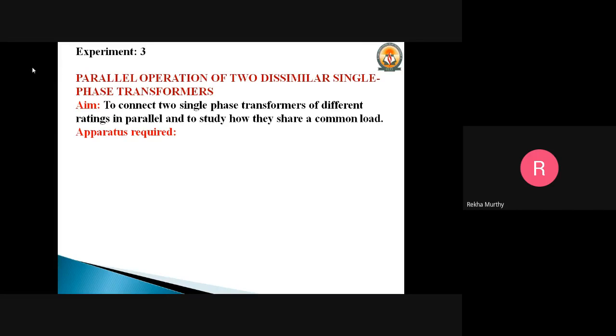So what are the conditions to be satisfied? The primary winding of a transformer should be suitable for the supply system voltage and frequency, and the transformers should be properly connected with regard to polarity. The voltage rating of both the primaries and the secondaries should be identical, that is, the same transformation ratio. The fourth point is that the percentage impedance should be equal in magnitude, and it should have the same X by R ratio. So let us see how these conditions can be satisfied when more than two transformers are connected in parallel, and how the power is shared by each of the transformers.